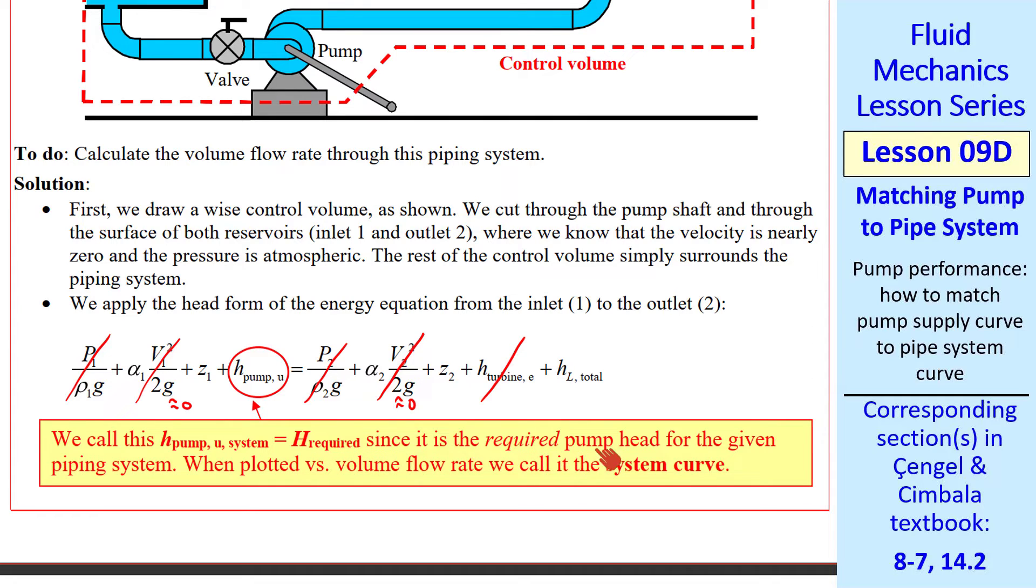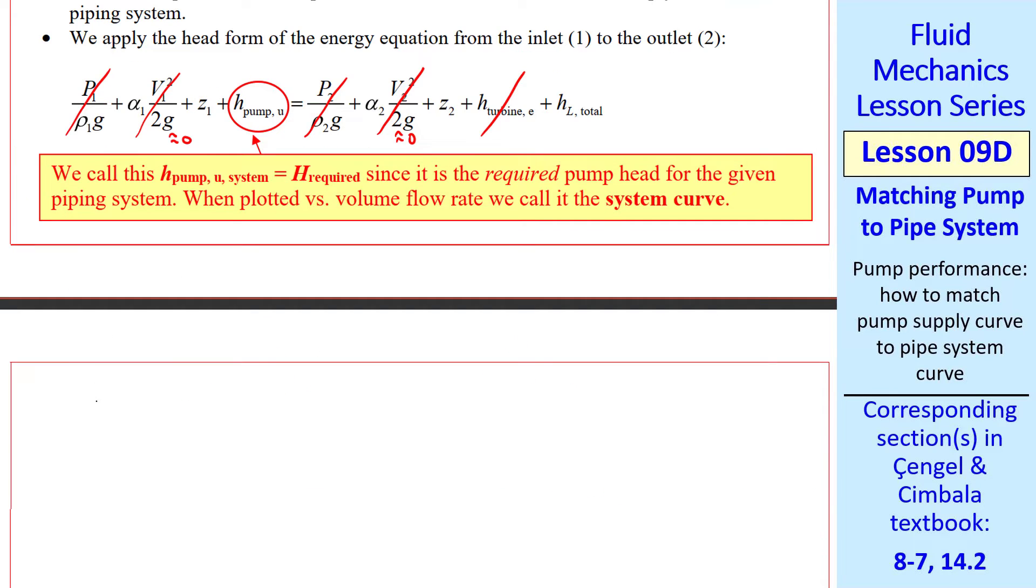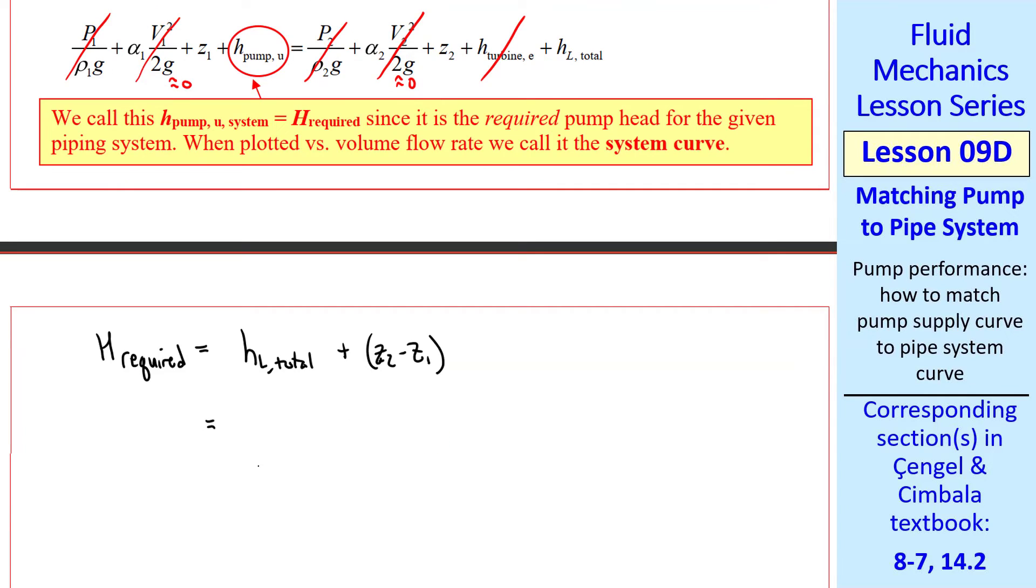It's the required pump head for the given piping system. When we plot this head, it will be our system curve. So this equation reduces to H required equal HL total plus Z2 minus Z1. This is similar to what I showed in the demo. So that submersible pump had to overcome irreversible losses through the tube, plus an elevation difference as I moved the outlet of the tube up.